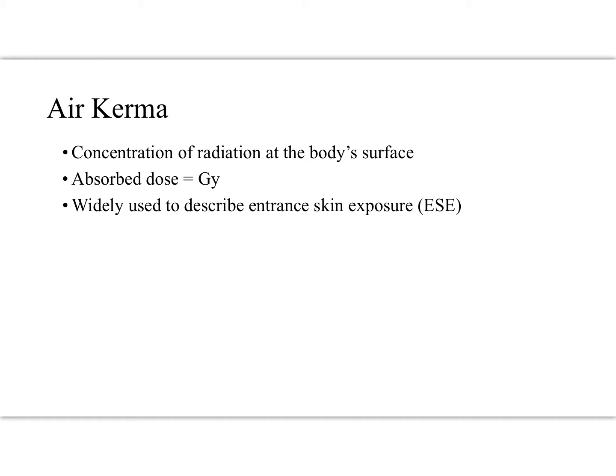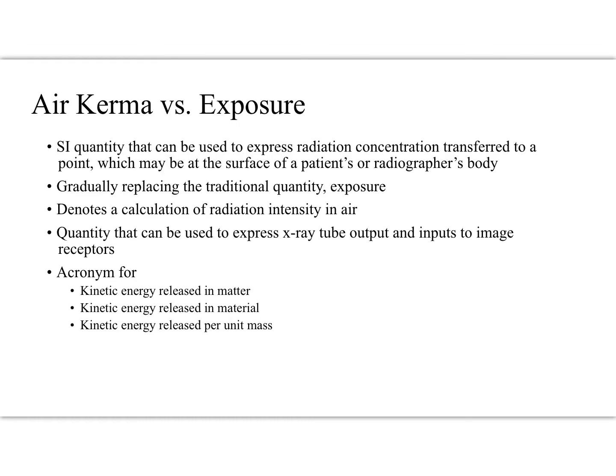Air kerma is actually translating that to the body — the concentration on the body surface — so it's relating exposure to organic systems. Air kerma is what we generally think about things; we tend to think about things in a simplified way and air kerma kind of stands in for exposure. We use it widely to describe an entrance skin exposure. So if I walk outside and there's sunlight, this is the amount of sun that's like striking my skin — the exposure as it were to my skin. It's different from exposure, but we kind of draw an equal sign between them. Air kerma is gradually replacing these traditional quantities of exposure, and we used to see things expressed in roentgen but we're seeing that less and less. It denotes that we've calculated what the radiation intensity was in air and then translated it to that surface.